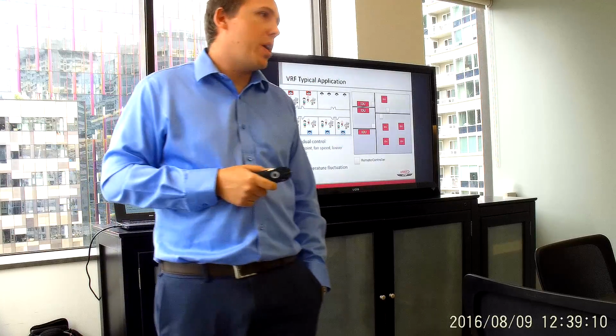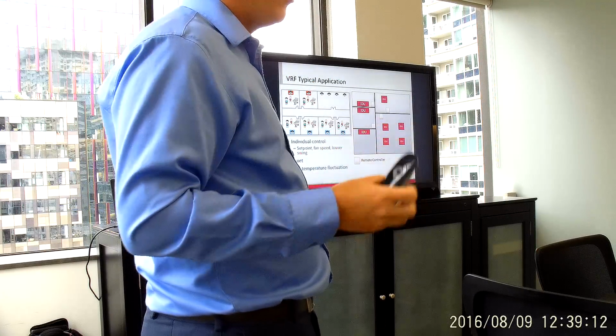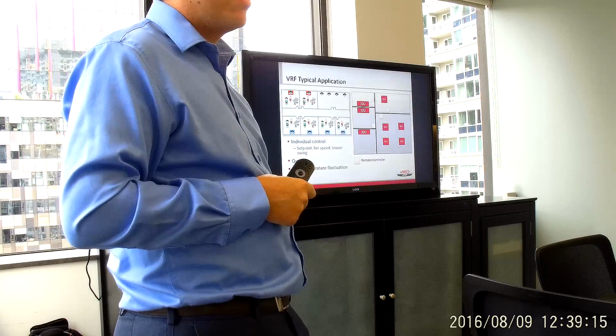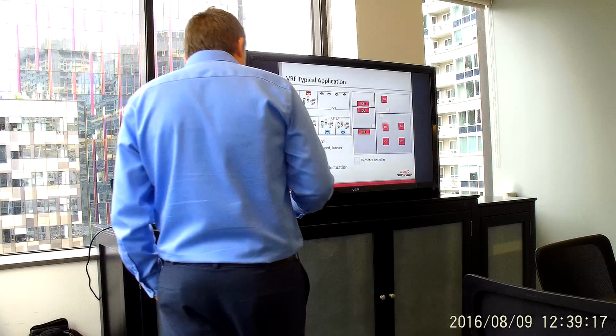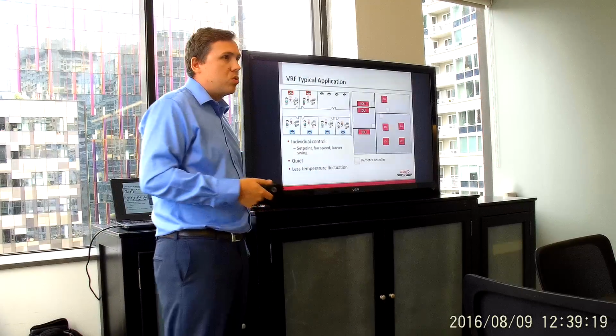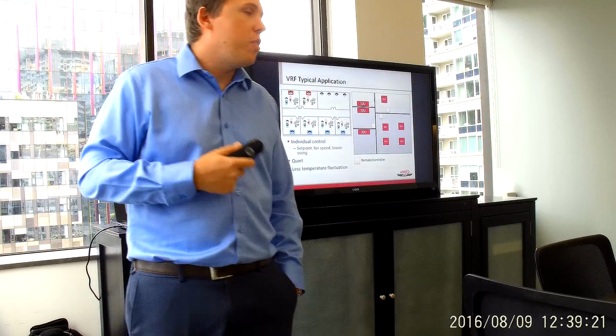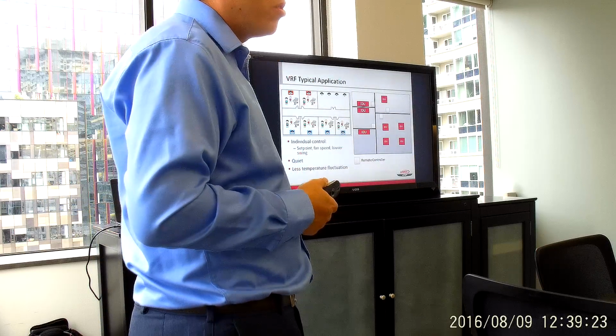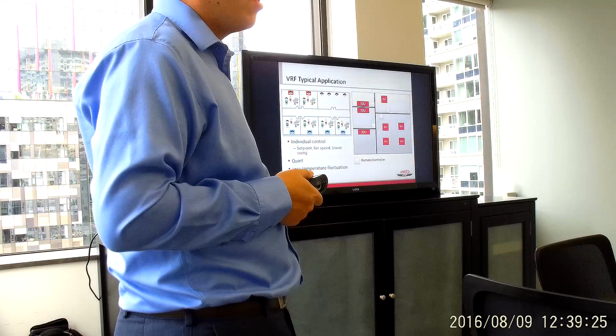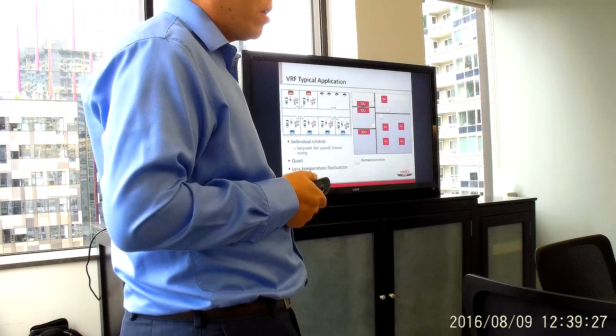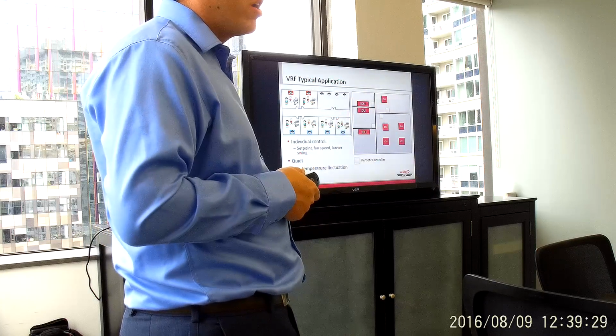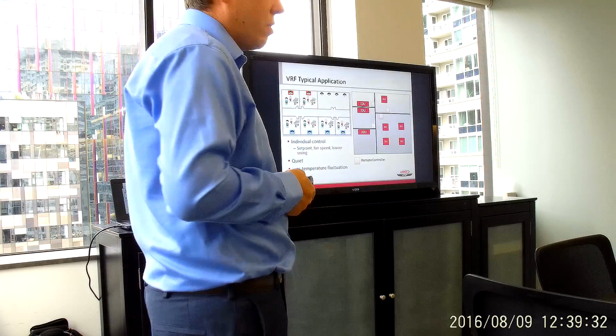Why not use a rooftop package unit? A lot of guys will say, oh, we need to use a DOAS, or makeup air unit. DOAS and makeup air units are really there for close control of fresh air supply. When you're feeding into the back of a fan coil unit, that fan coil unit doesn't mind if there's a temperature swing of 3 or 4 degrees. It's not concerned about that, because it's going to operate accordingly. It's such a small volume that goes into that fan coil unit.